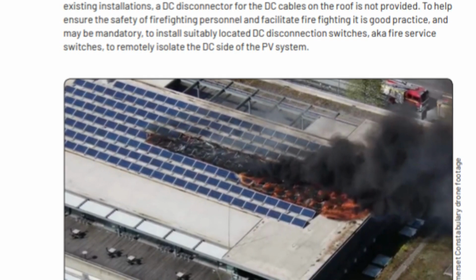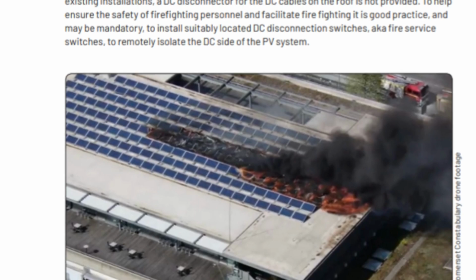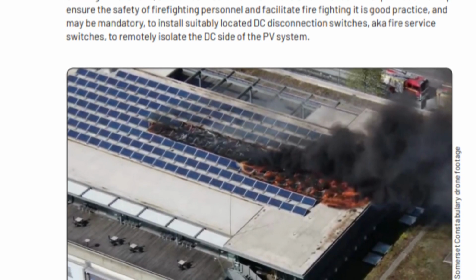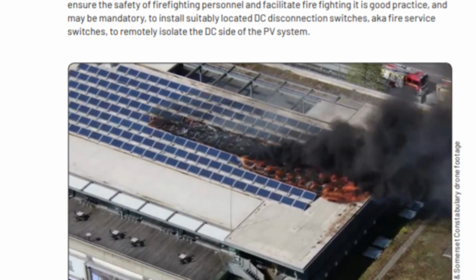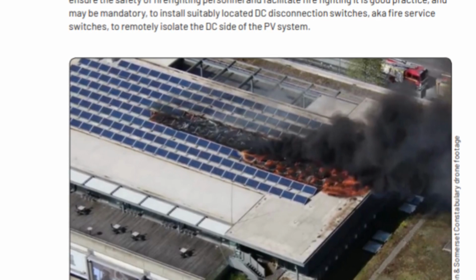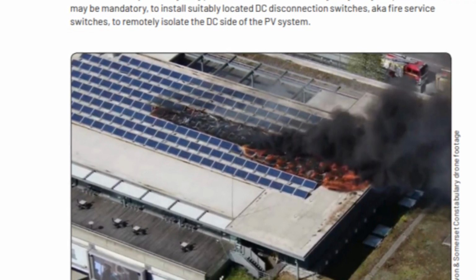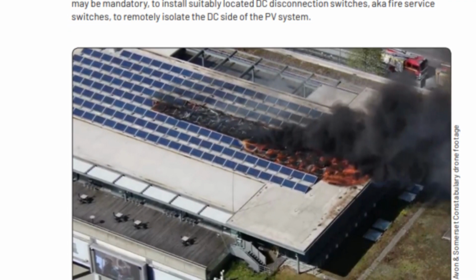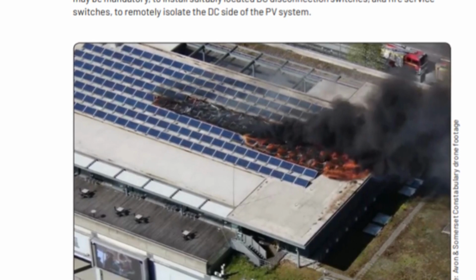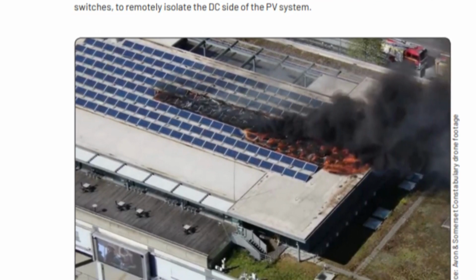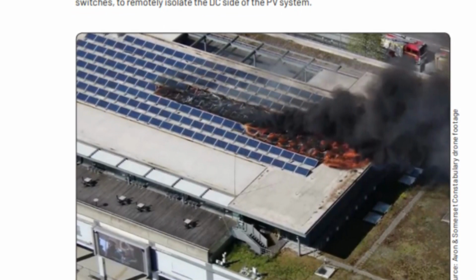To help ensure the safety of firefighting personnel and facilitate firefighting, the document recommends the installation of suitably located DC disconnection switches, also known as fire service switches. These switches allow for the remote isolation of the DC side of the PV system. This is considered good practice and may even be mandatory in some installations.